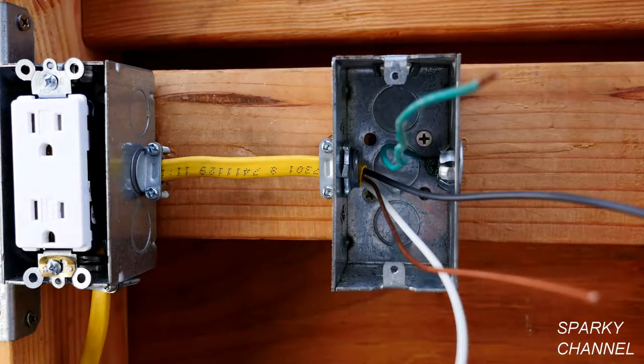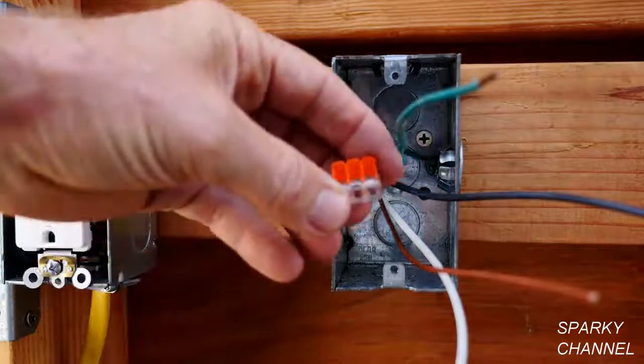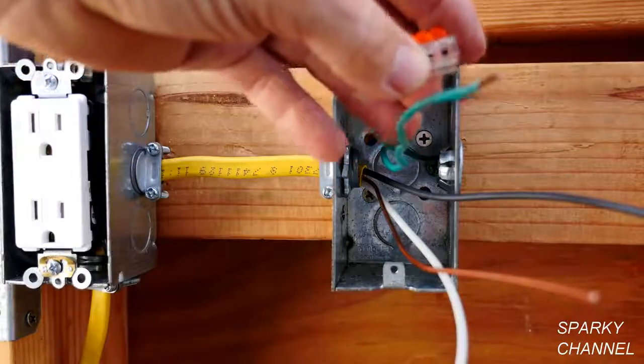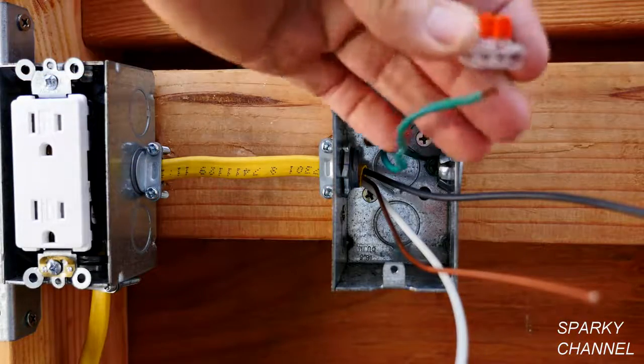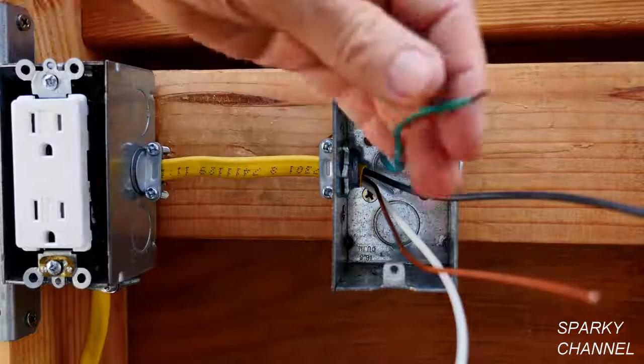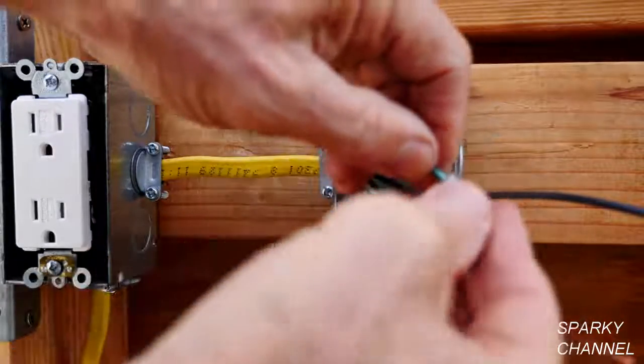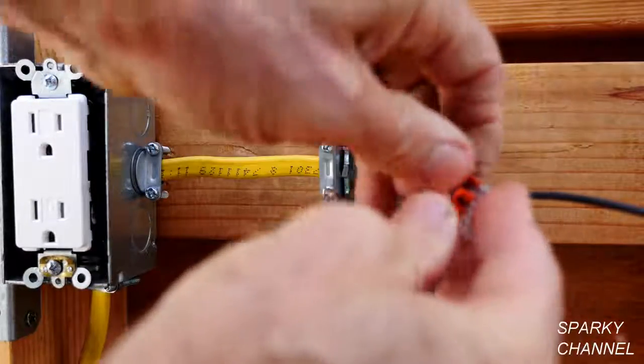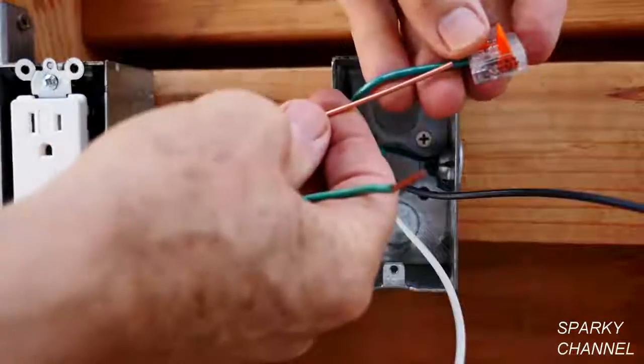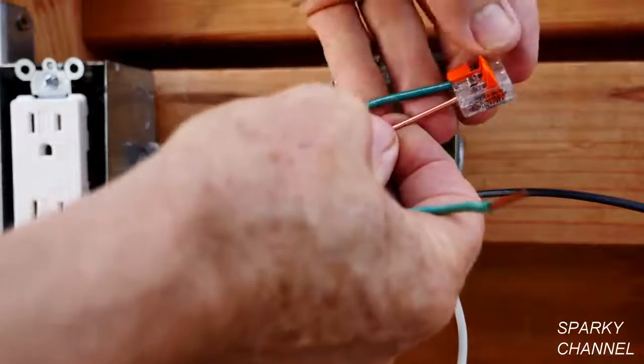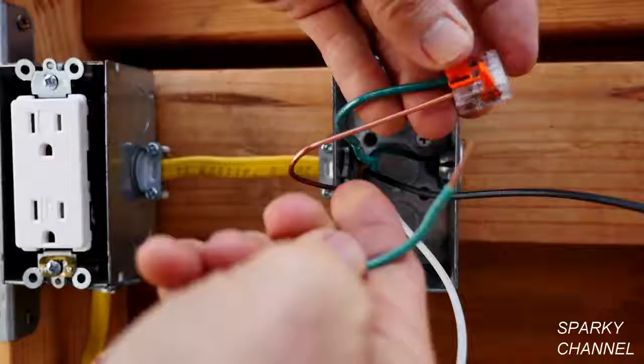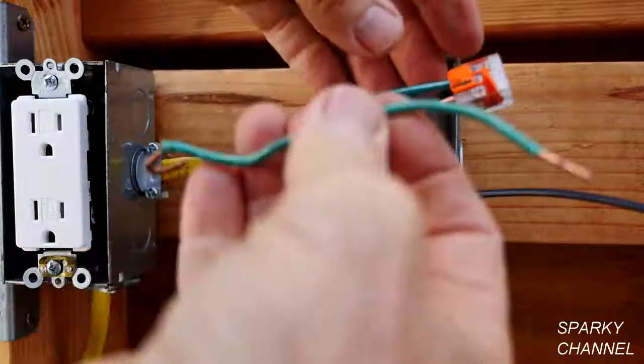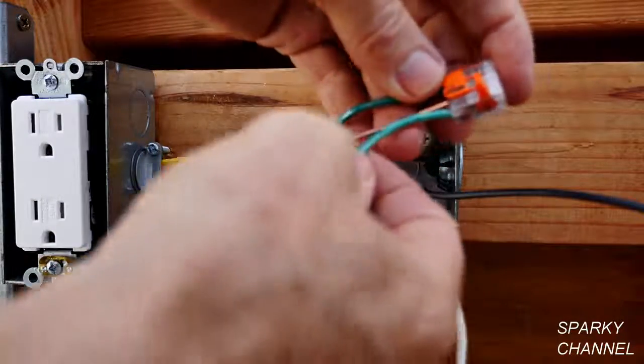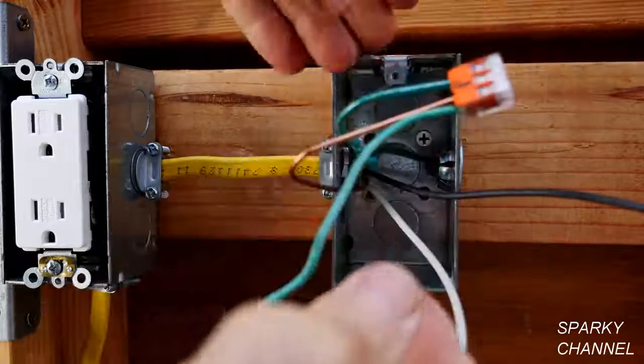Now I'm going to install a receptacle in this box, and first I'm going to hook up the grounds, and I'll use a 3 connector Wago lever nut. First I'll put the grounding pigtail that bonds the box. Then I'll hook up the ground that's coming from the upstream receptacle. And now this is a pigtail that I'm going to run to the receptacle itself.